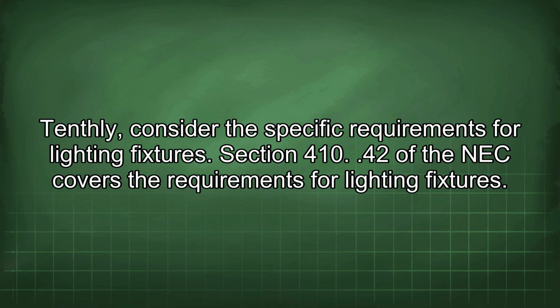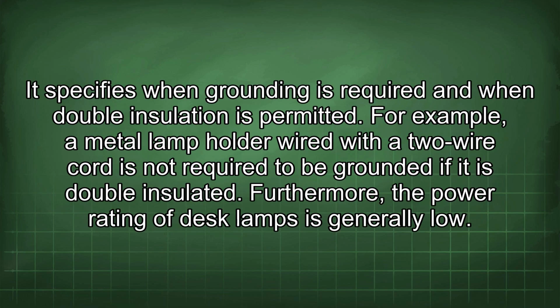Section 410.42 of the NEC covers the requirements for lighting fixtures. It specifies when grounding is required and when double insulation is permitted. For example, a metal lamp holder wired with a 2-wire cord is not required to be grounded if it is double insulated. Furthermore, the power rating of desk lamps is generally low.